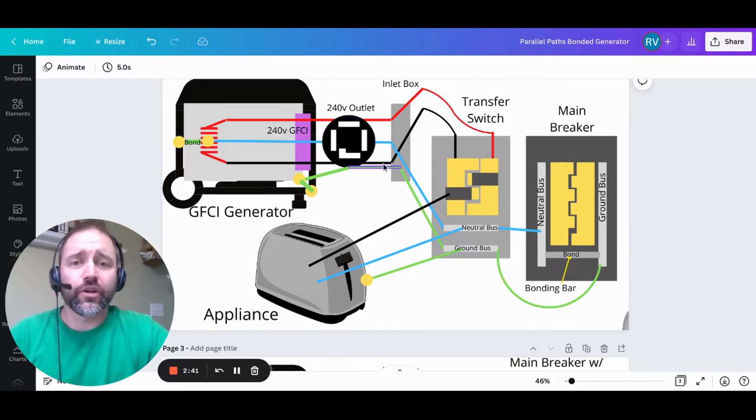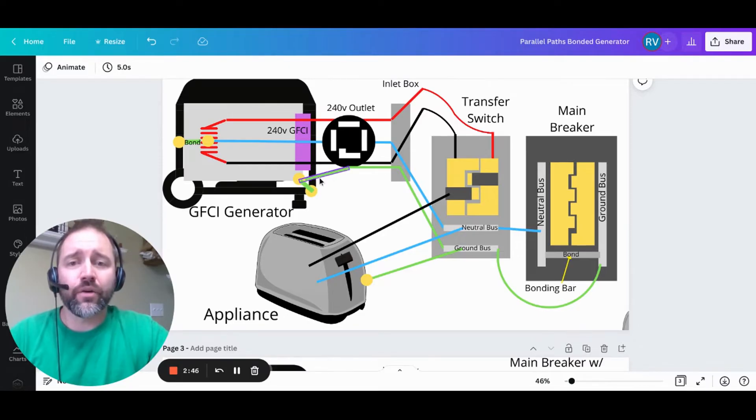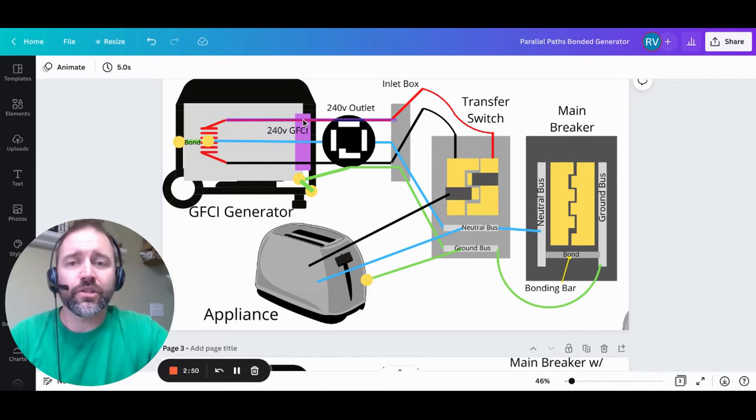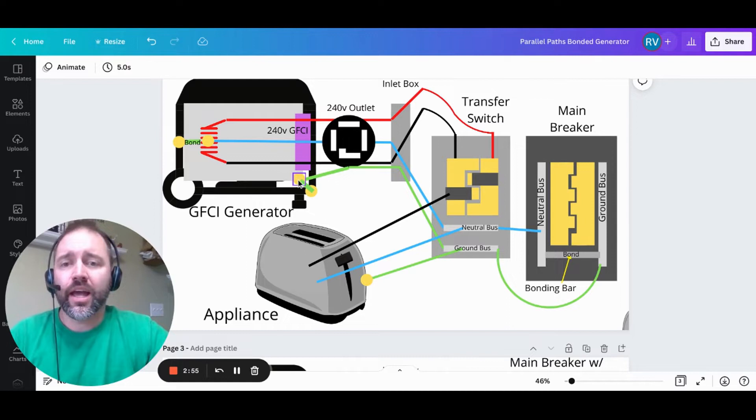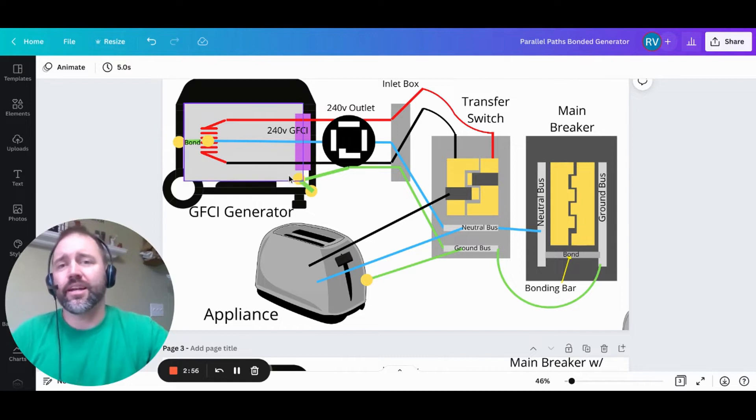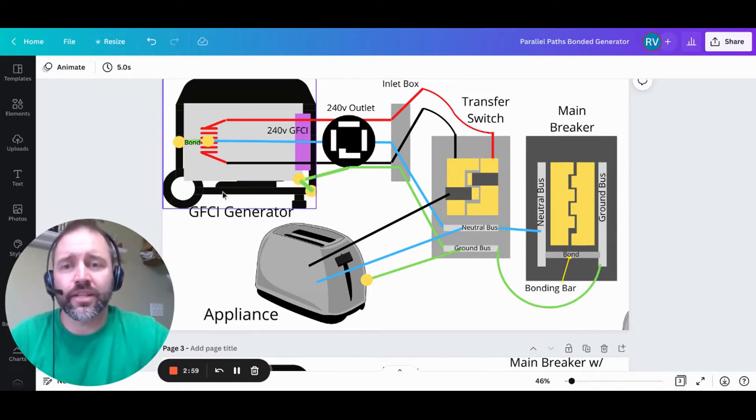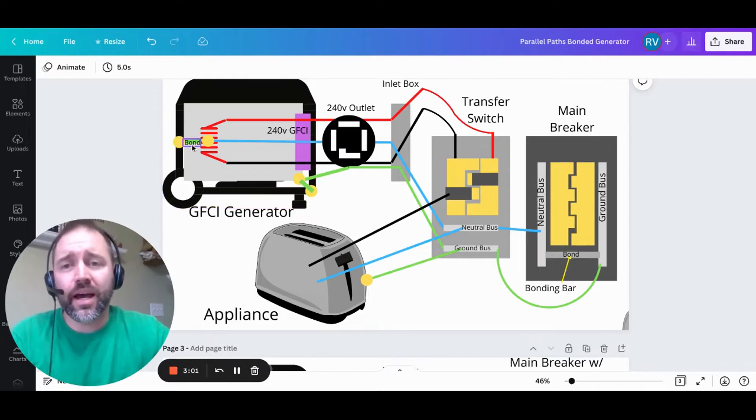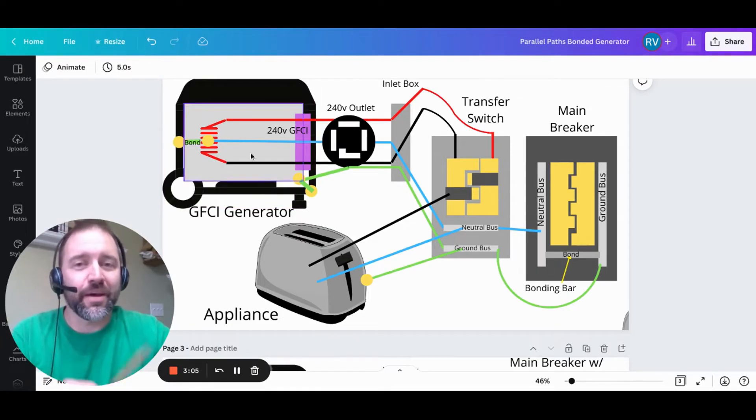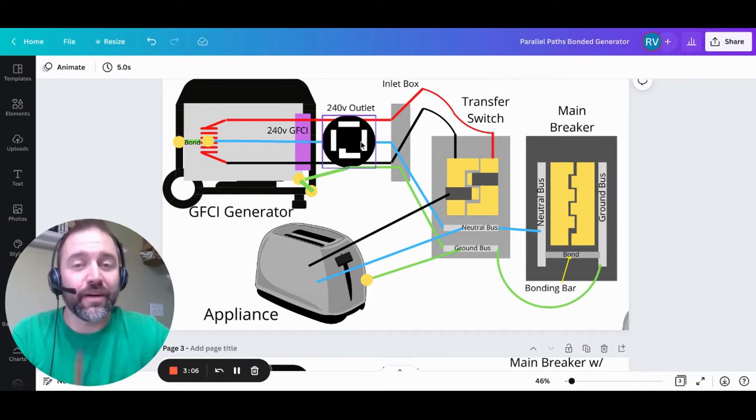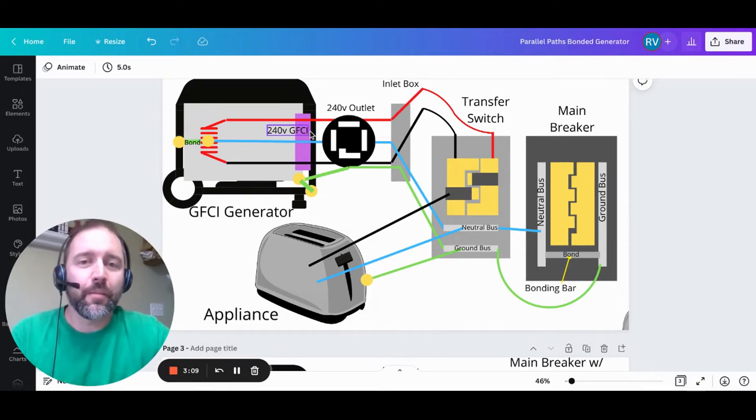Now, you'd plug in your cord, which would be here, and then into your house, the inlet box here. There is a ground wire that goes to the 240-volt outlet, but it does not pass through the GFCI breaker. It instead attaches internally to the generator, and then everything metallic on the generator itself is all grounded. Let's just keep following the electricity downstream of the GFCI breaker.